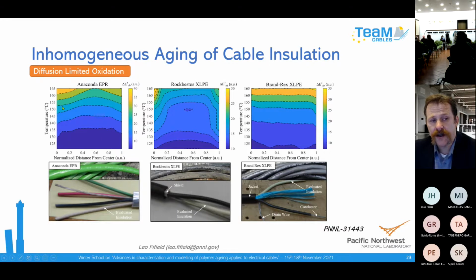So we saw in this example of EPR on the left, at a lower temperature of aging, it was more homogeneous through the thickness. But as we increased the temperature up to 165 degrees C during aging, we saw more of this effect of more rapid aging at the edge. Similar results were observed for this XLPE, but we observed that this kind of behavior is material dependent. In this Brand Rex XLPE, even at the highest temperatures, we saw more homogeneous aging throughout the thickness.